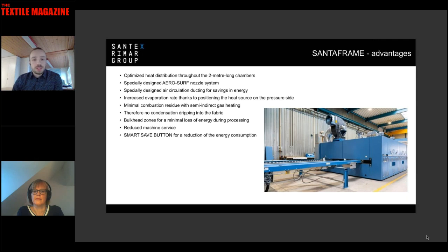Minimal combustion residue by utilizing semi-indirect gas heating as an alternative to thermal oil heating during the heat setting or curing processes. Increased performance and precise temperature control during processing without any energy loss by introducing bulkhead zones at the inlet and outlet. Savings in energy consumption as a result of a specially designed built-in exhaust air circulation duct, which in combination with heat recovery units reduces installation costs. Reduced machine service and maintenance with less time required for cleaning, the retractable nozzles, ease of access to the heat exchangers, and the exhaust air ducts which are located inside of the frame.